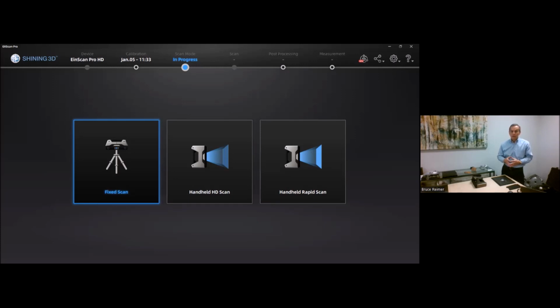Thirdly, if you plan to relocate the unit to maybe a room down the hallway in the same building, or perhaps pack it up for a road trip to do an offsite scan, you'll want to recalibrate the unit once you're set up and ready to go. And then lastly, if you're in the middle of a scan and you find that the unit doesn't seem to be operating quite as normally as you would expect, I find that well over 95% of the time, recalibrating the unit addresses the issue. So with that as the backdrop, let's go ahead and dive into the calibration.